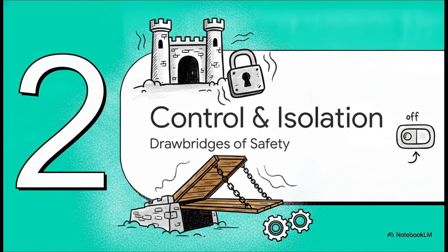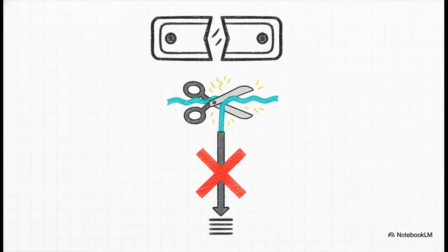Moving on to part 2, taking control and isolation. Think of these as the gates and drawbridges of our fortress. When we isolate an electrical circuit to work on it, we obviously want to sever the live power lines, the active conductors, so the person doing the maintenance doesn't suddenly start glowing in the dark, right? But here's the thing. The standard is incredibly strict about this. An isolation device must never, ever interrupt an earthing conductor.